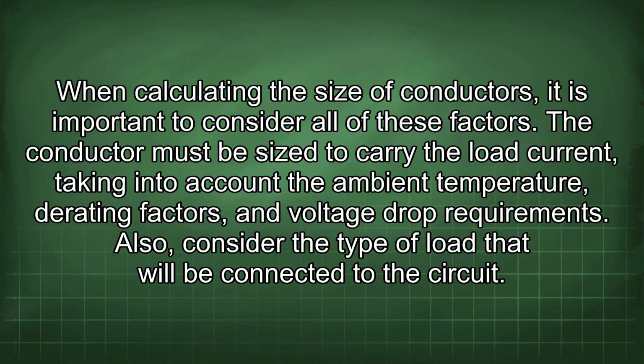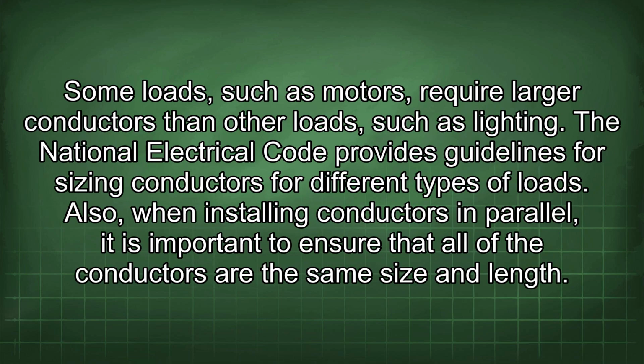When calculating the size of conductors, it is important to consider all of these factors. The conductor must be sized to carry the load current, taking into account the ambient temperature, derating factors, and voltage drop requirements. Also, consider the type of load that will be connected to the circuit. Some loads, such as motors, require larger conductors than other loads, such as lighting. The National Electrical Code provides guidelines for sizing conductors for different types of loads.